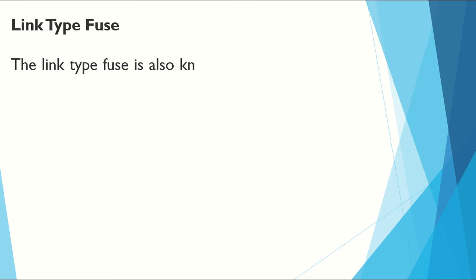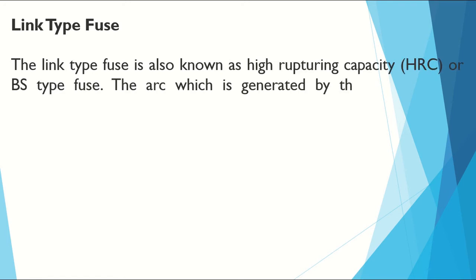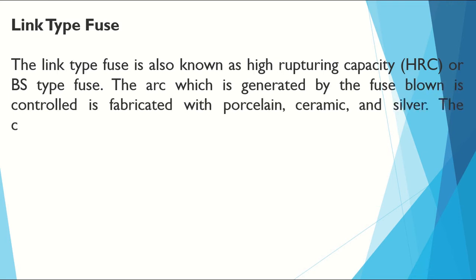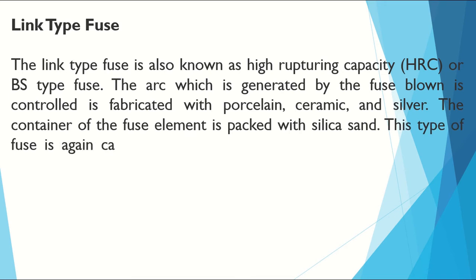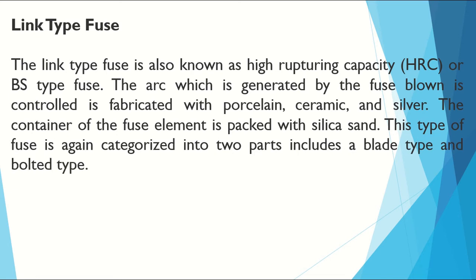Link type fuse, also known as High Rupturing Capacity (HRC) or BS type fuse. The arc generated when the fuse blows is controlled; it is fabricated with porcelain, ceramic, and silver. The container of the fuse element is packed with silica sand. This type of fuse is categorized into two parts: blade type and bolted type.